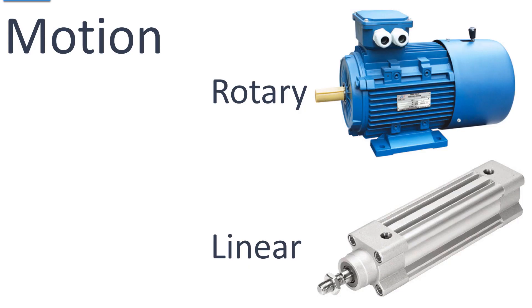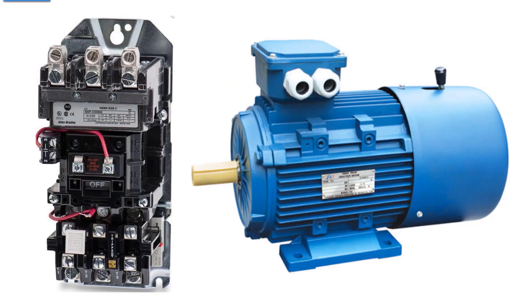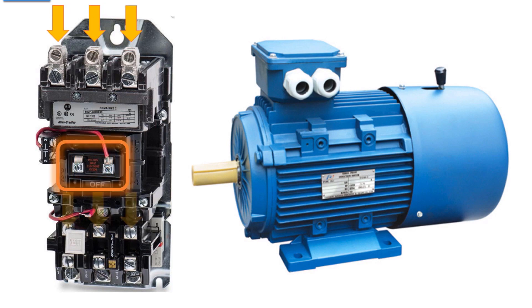One of the goals of a digital output from a PLC is motion, and there are two forms of motion available: rotary and linear. Rotary motion is controlled by a motor starter — it's actually a relay with motor overloads. You apply three-phase power, and when you energize the coil, current flows through the overloads and out T1, T2, T3 over to T1, T2, T3 on that three-phase motor.